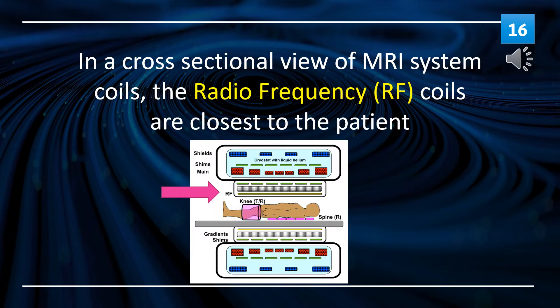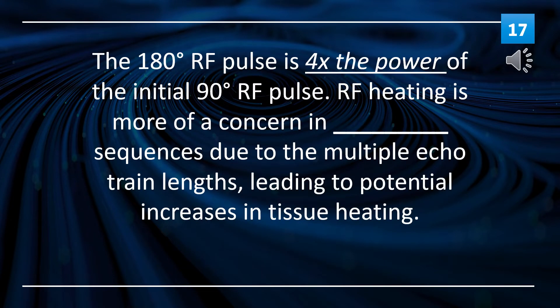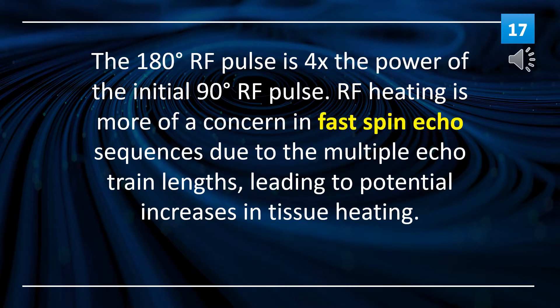In a cross-sectional view of MRI system coils, what coils are closest to the patient? Radio frequency coils are closest to the patient. The 180-degree RF pulse is 4 times the power of the initial 90-degree RF pulse. RF heating is more of a concern in fast spin echo sequences due to the multiple echo train lengths, leading to potential increases in tissue heating.